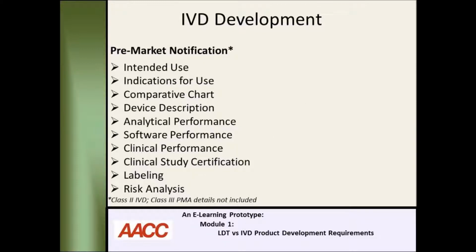As with the LDT developer, this list shown here for IVD developer responsibilities is only a subset of the entire process of getting their product to market. The components of the pre-market notification, or 510K, are shown here, and all elements tie back to the intended use of the product. As a result, the planning of studies, the generation of data, and the required statistical power will be quite different from an LDT developed in a specific clinical laboratory.